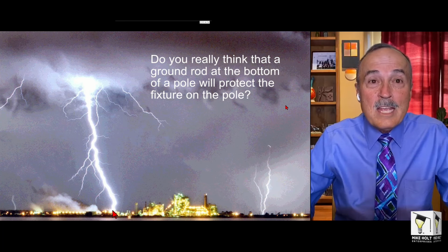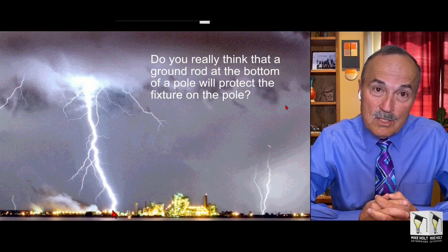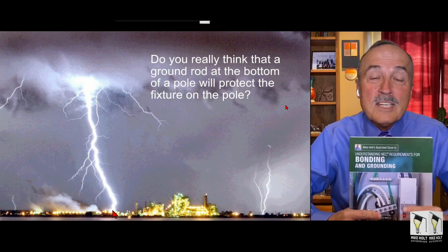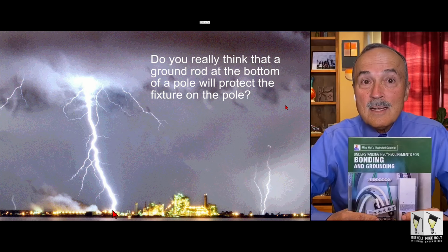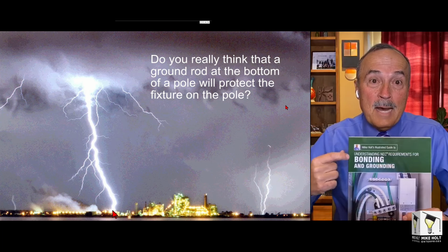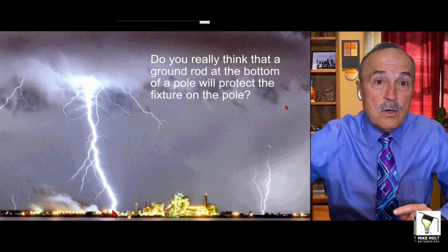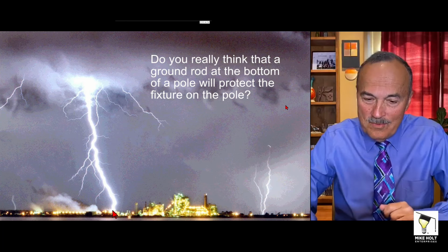Of course not. People were driving ground rods because they thought that's what made it safe from electricity, because it was grounded. Grounding doesn't make anything safe. Bonding, as a matter of fact, if you notice, my book is the only book that's titled Bonding and Grounding. Every other book is titled Grounding and Bonding, because the most important thing we have to do is what? Bonding. Now there are grounding requirements in the code, and you need to know those, and we've covered those many, many times already. All right, so no.